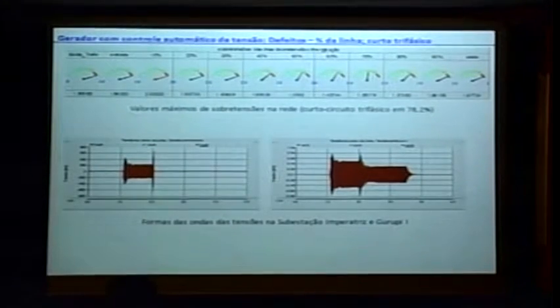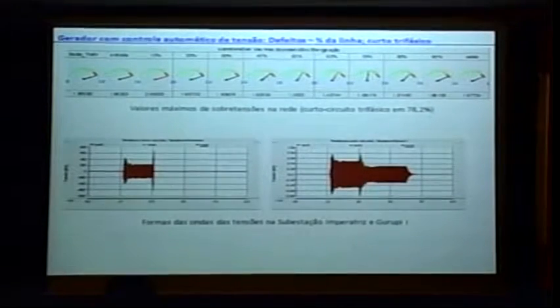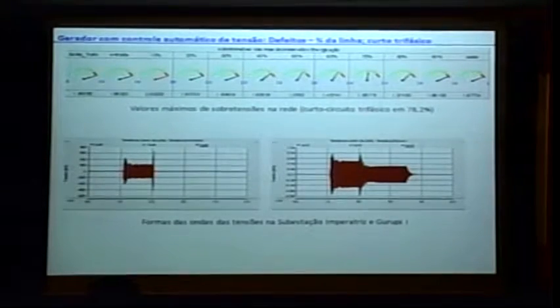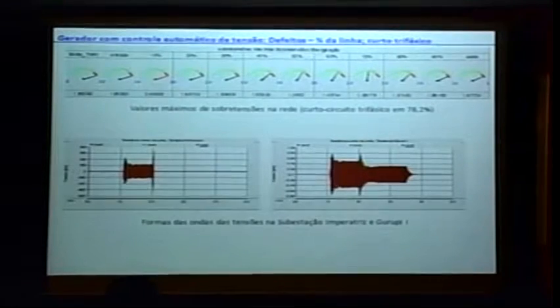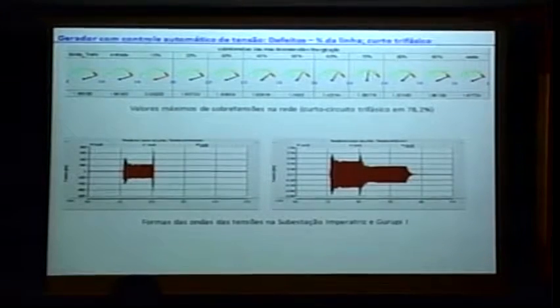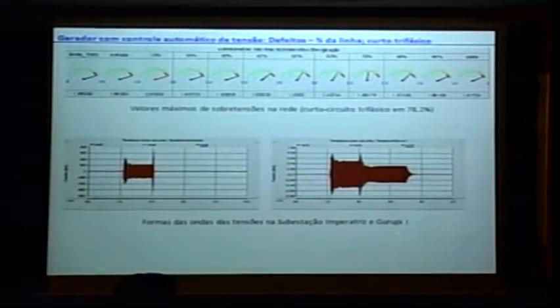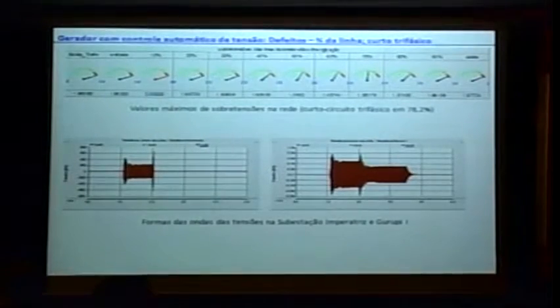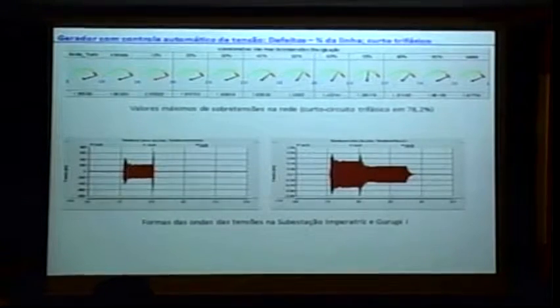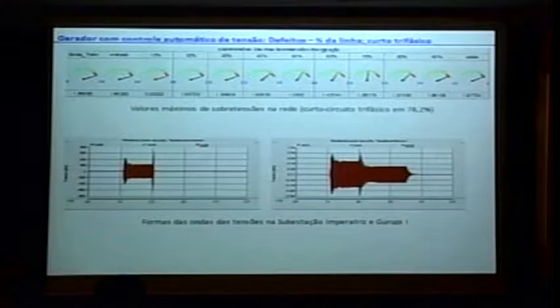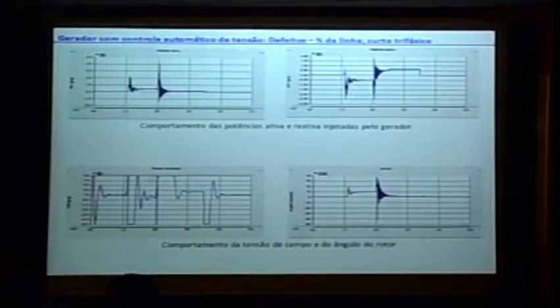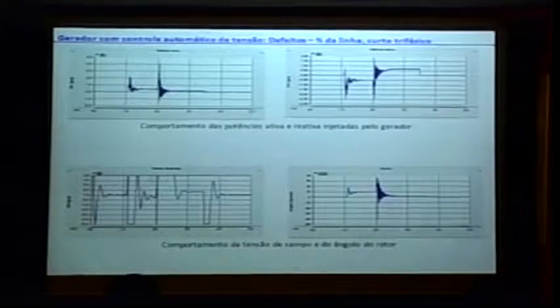So this shows the voltage in Imperatriz. It falls to 0 upstream of the gap because the whole part of the line was turned off. That would be the transient of voltage in Imperatriz here. From Imperatriz onwards was turned off, and from Imperatriz to Serra da Mesa the line is still energized but with under voltage, 0.4, 0.3 pu of voltage. Even after the elimination of the fault, the gap continued discharging energy in Imperatriz.